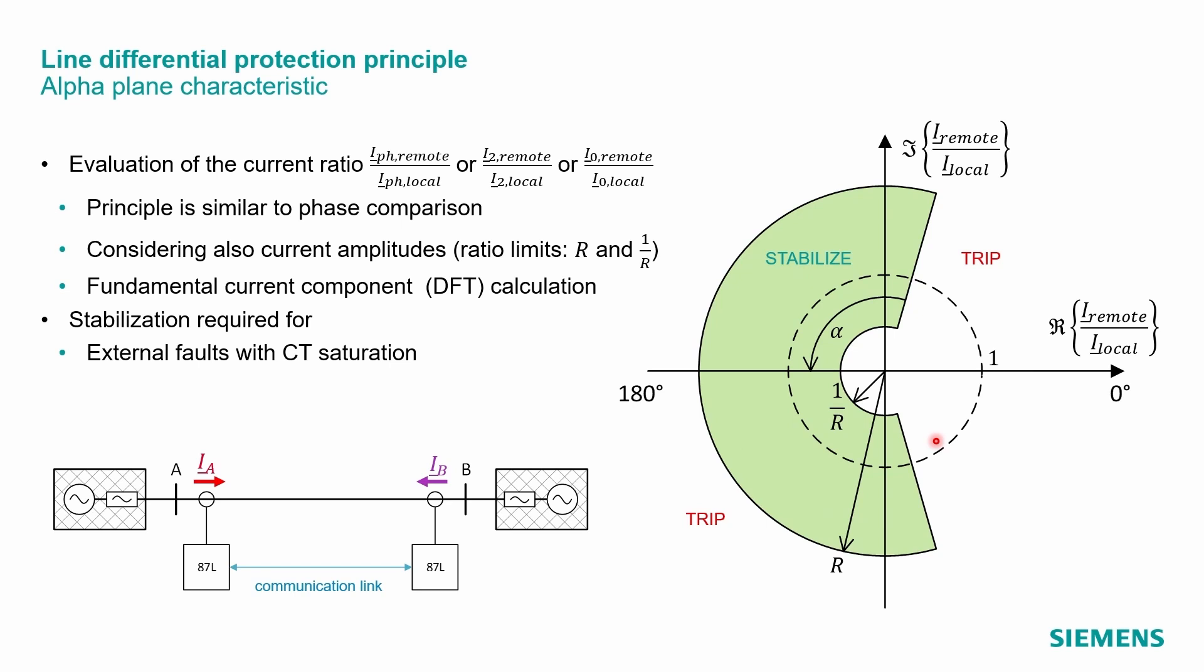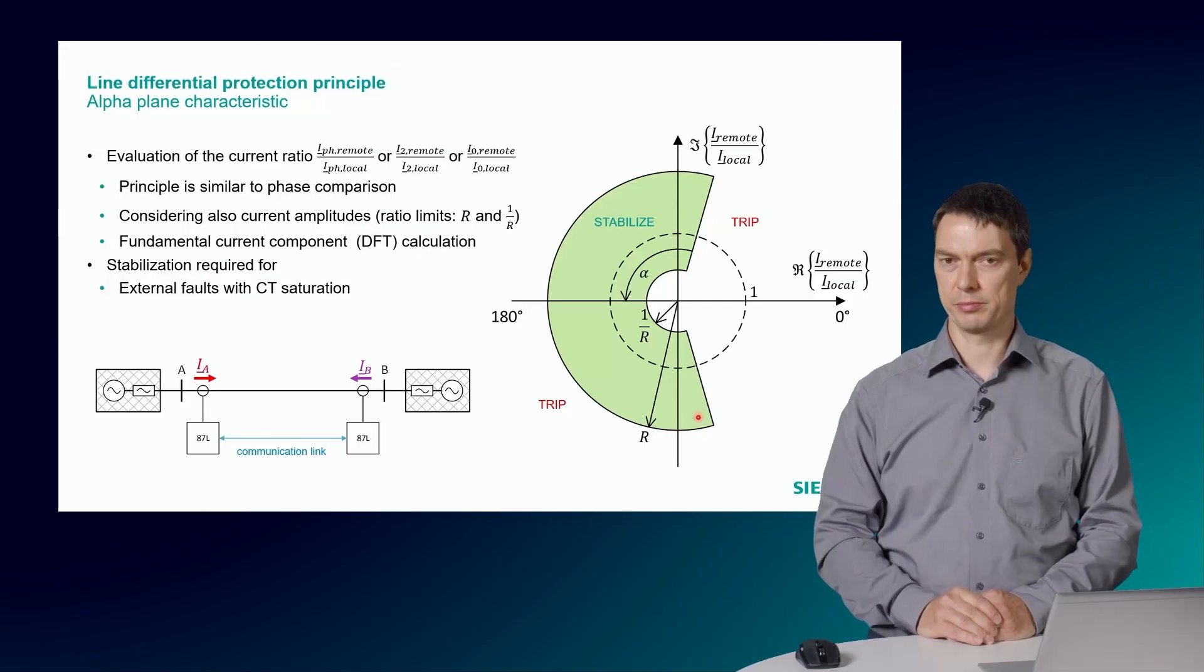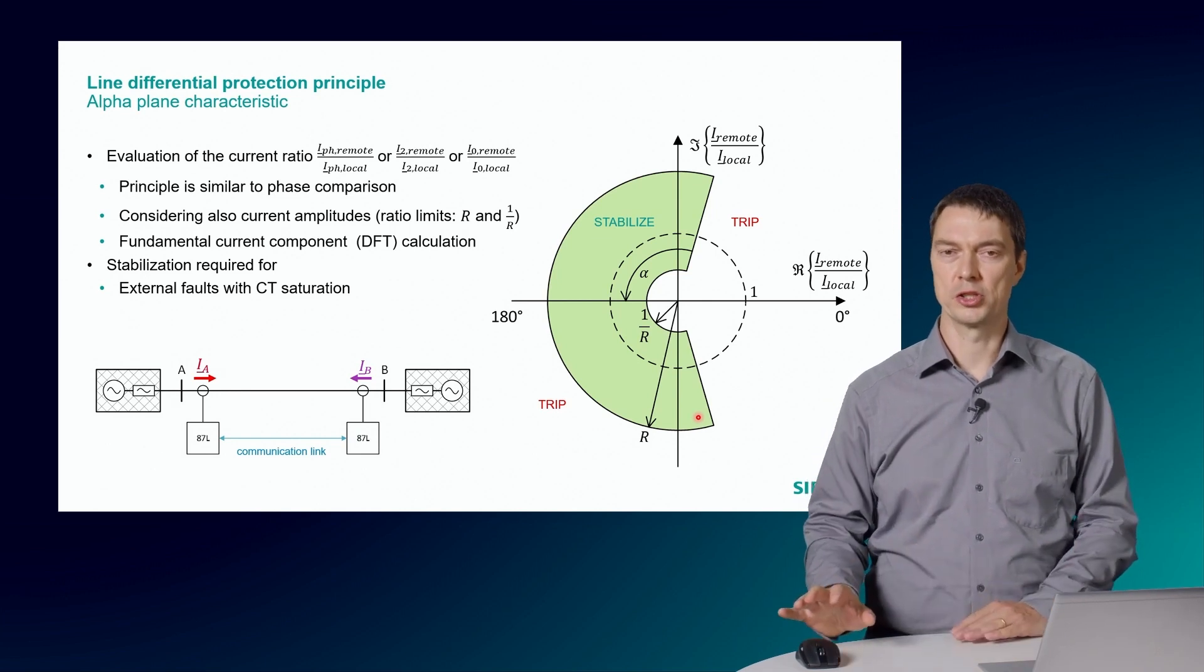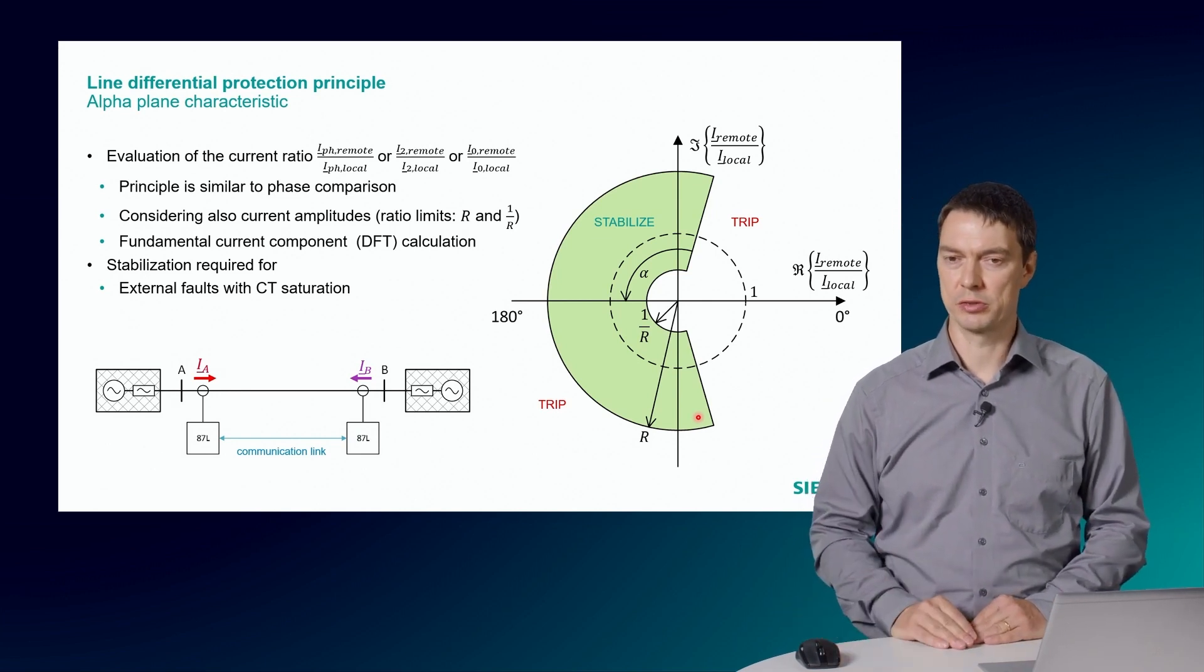Some current amplitude difference shall be acceptable. Therefore, we set a maximum ratio R in this device. This defines an inner and an outer radius of this stabilization area. The maximum phase angle is defined by the phase error to be considered, similar to the previous explained phase comparison principle. Also, the alpha-plane needs some additional stabilization for CT saturation, which is not shown here.